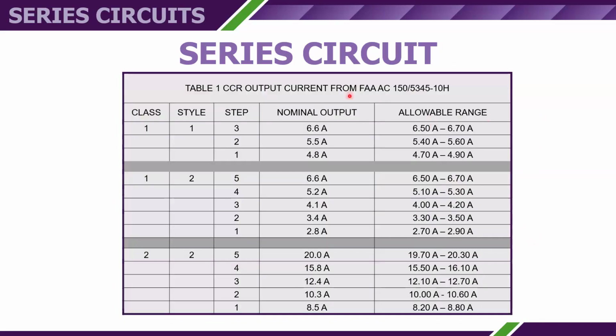This is the table from Advisory Circular 150/5345-10H, which is the advisory circular that tells the manufacturer how to manufacture constant current regulators. It also gives us the information on what we need to know for setting the current on our regulators. We have a 1/10 of an amp tolerance for our available range on the constant current output for a 6.6 amp circuit, and 3/10 of an amp tolerance on a 20 amp circuit.